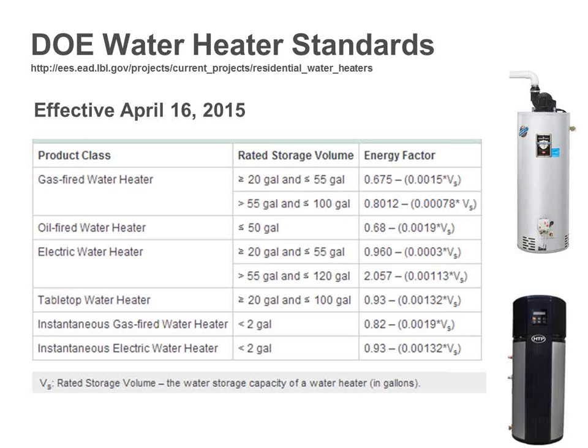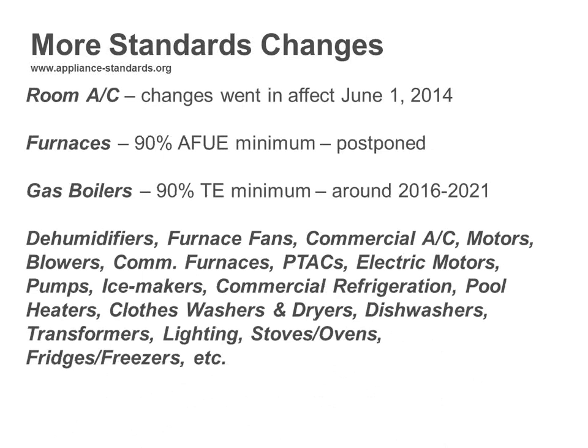And then the really big change is on the electric water heater side, 55 gallons and up. You'll see there it goes to an energy factor of 2 point something. Well, that's basically 200 and some percent efficient. So the only current technology to get you there is a heat pump. So basically, it's stating that all electric water heaters, 55 gallons and larger, have to be heat pump water heaters. So if you're not familiar with heat pump water heaters, this is probably a good summer and fall to get familiar with those. And there are tons of other standards that change that the Department of Energy or other federal entities govern. These are some other ones that are coming up.